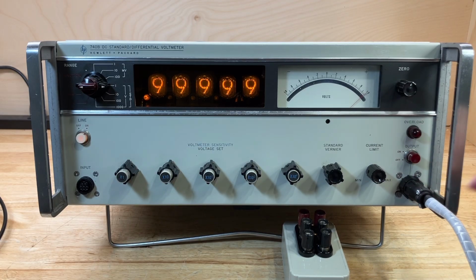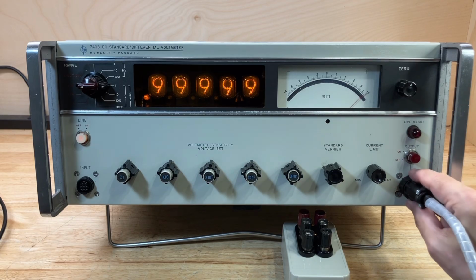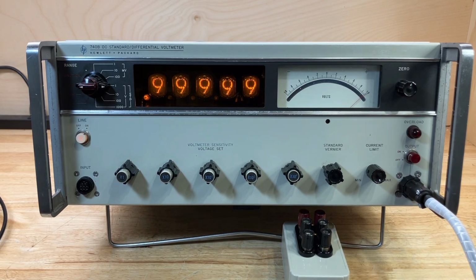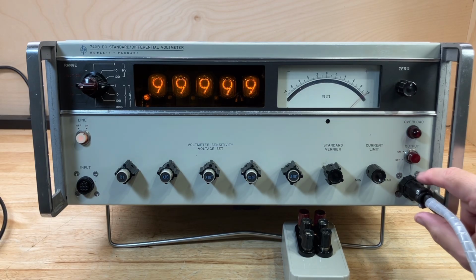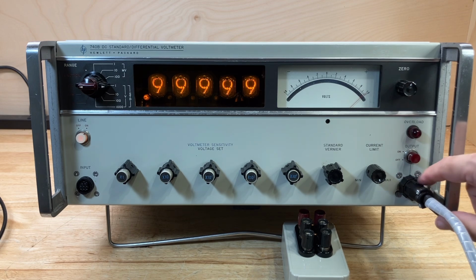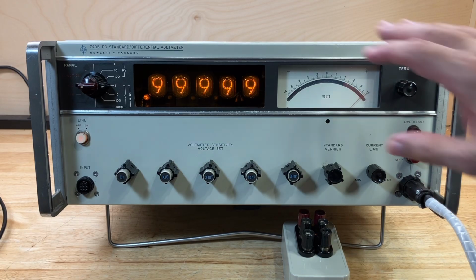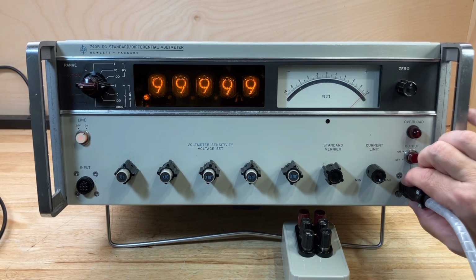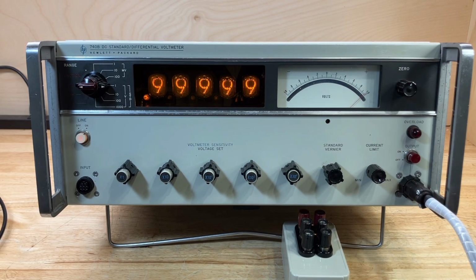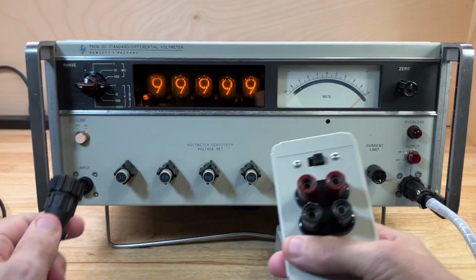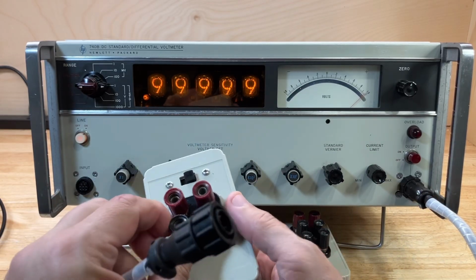These AMP connectors are what I'll use to replace the original connectors that come with the instrument, which are no longer available. I'm hoping these, even though only rated at about 500 volts rather than the full 1,000 volts, will work okay since I wired them internally with large separation between the high voltage conductors. The instrument isn't fully working right now, so I can't test that out yet. But in any case, I made a similar box for the input connector cable assembly to replace the missing cable assembly on this instrument.